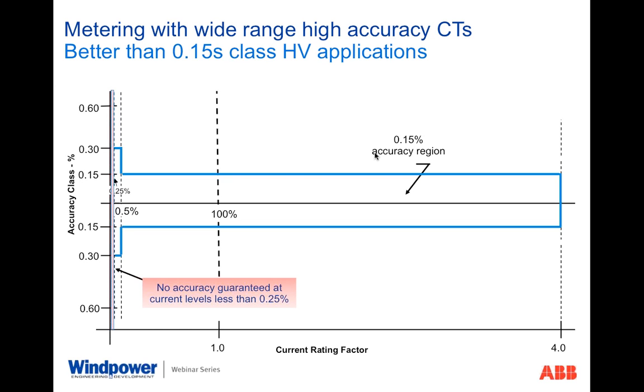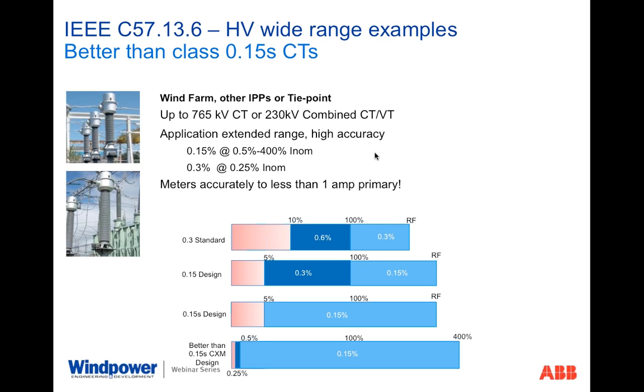We go down to 0.25% of nominal current in the 0.3 revenue metering class, which is an important distinction because you want to know what the guarantee is as low as you can go. And in this case, 0.25% takes it all the way down to just about the level of detection in the meters. So we're really getting into the point of where the instrument transformers are as accurate or more accurate than the solid-state meters they supply. So it's extremely important that advancements over the last 12 years have really taken as much of a turn as I've seen in 30 years of instrument transformer development.